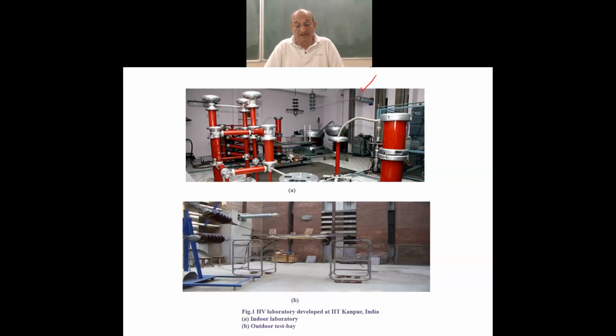With the help of this wall bushing, which can withstand all the maximum voltages I described, AC, DC, and power frequency, the voltages can be taken out. And in figure B at the bottom, you see the wall bushing coming out into the open area. So the problem of limited space for the experimental setup, where you want to apply the high voltage, is resolved with the help of this wall bushing, and all the voltages generated inside can be taken out to the open air bay.